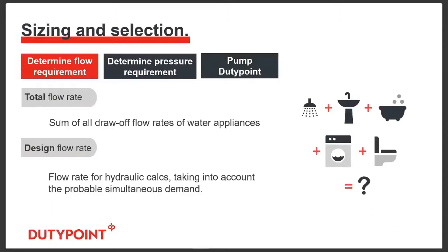And as designers, it's important to intelligently think about that. So for example, a city centre sort of business-oriented hotel is going to have a peak demand, say between 6:30 a.m. and maybe about 8 a.m. because you've got people getting up to go and do a day of work. Whereas maybe a leisure resort is going to have a slightly different pattern, and equally a student accommodation building is going to have a different pattern.